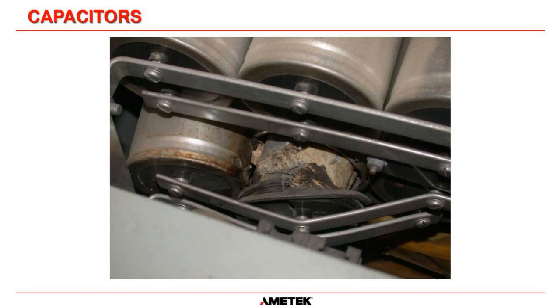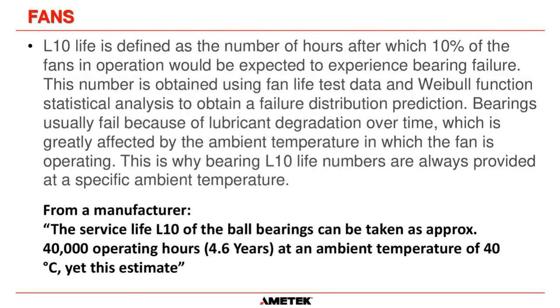And in some circumstances, this can cause fire. And if that capacitor went on fire, then obviously the heat is going to rise to this capacitor here and go to these other capacitors here. And that can cause those other capacitors to go on fire. So heat and age are an enemy of a DC electrolytic capacitor. So that is why we recommend they are replaced every 10 years. Okay. Now for fans.